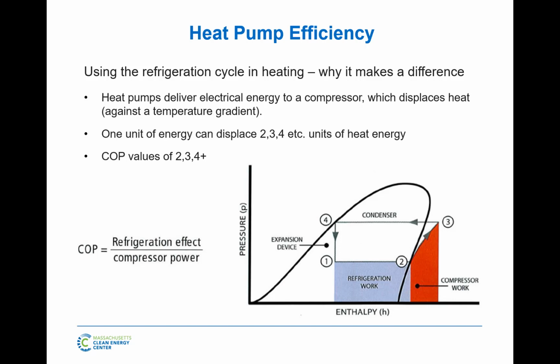So unfortunately, we don't have what we like to refer to as an ICOP, which is a COP at 75% load, 50% load. That doesn't exist yet. So in heating, it makes it much harder for us to demonstrate that, even though gas is a lot cheaper than electricity, by a ratio of 3 or 4 or 5, our COPs are 2 or 3 or 4 or 5 at full load and way more at part load. That's very hard to demonstrate. But even looking at just full load values, if you start to graph it, you come up with what we call a transition temperature. And that addresses this gentleman's question earlier about where the heat comes from and how well it does it when it gets cold.